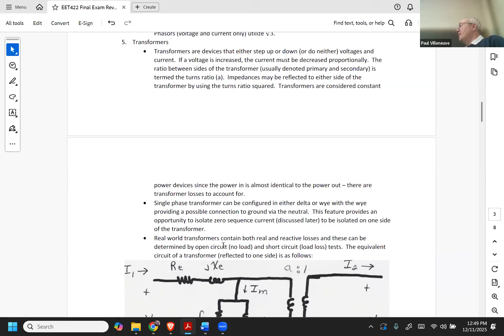You can do that practically up to about 225, maybe 300 kVA load, where you can just go off the shelf and buy a transformer. If you said, hey, I need a 300 kVA transformer, I'd tell you to go down to the local electrical supply - not Home Depot, but like Gilman - and they can order single-phase pole-mounted transformers. Then you just put them where you need to and wire them up, and they work beautifully. They're cheap, it's very easy. They're heavy - these things aren't light - but it's a much more efficient way than ordering a three-phase transformer from ABB or something like that.